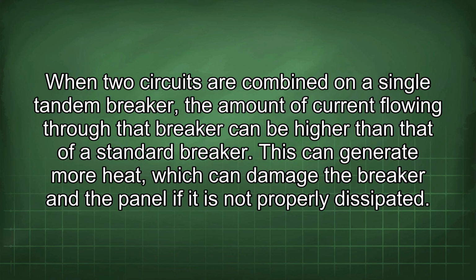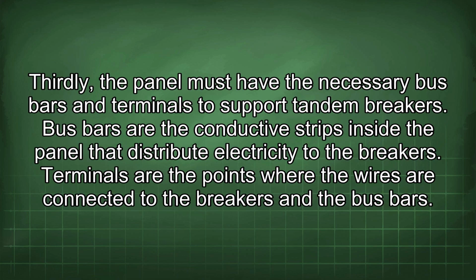When two circuits are combined on a single tandem breaker, the amount of current flowing through that breaker can be higher than that of a standard breaker. This can generate more heat, which can damage the breaker and the panel if it is not properly dissipated. Thirdly, the panel must have the necessary bus bars and terminals to support tandem breakers.